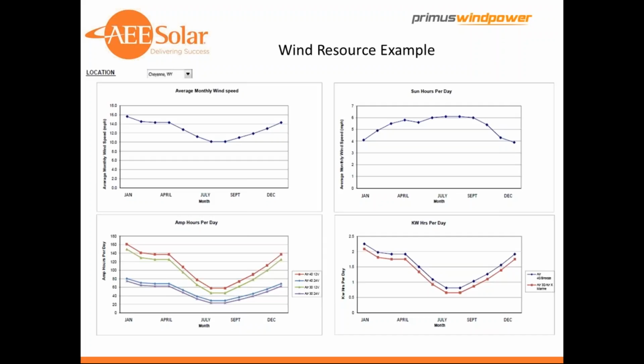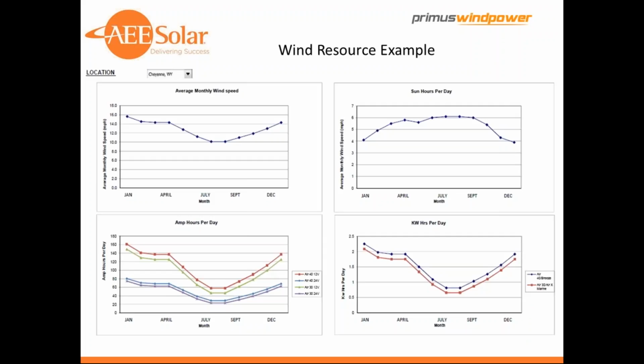Then the two bottom charts are showing amp hours produced per day and also kilowatt hours per day. You can see the difference in amp hours per day, for instance showing a difference between a 12 and 24 volt machine. Obviously, the amp hours are doubled at 12 volts than they would be at 24 volts, but it's the same amount of energy produced, which is the kilowatt hours per day shown in the lower right chart.